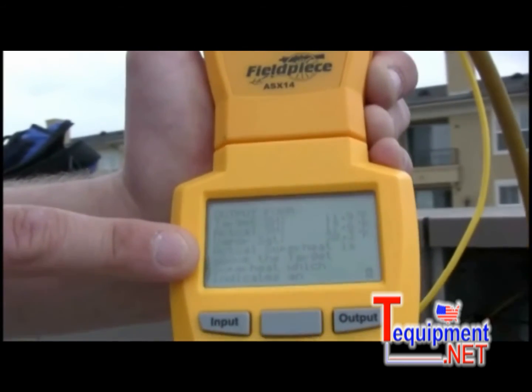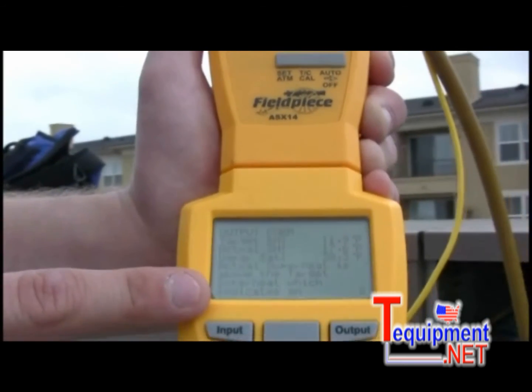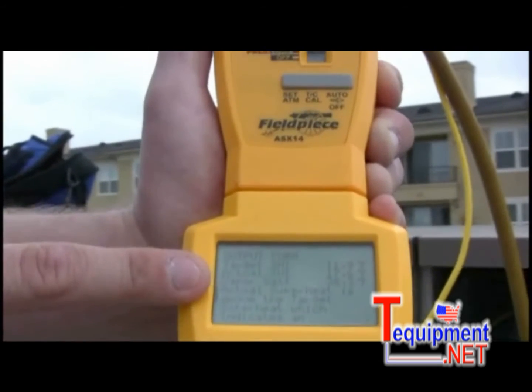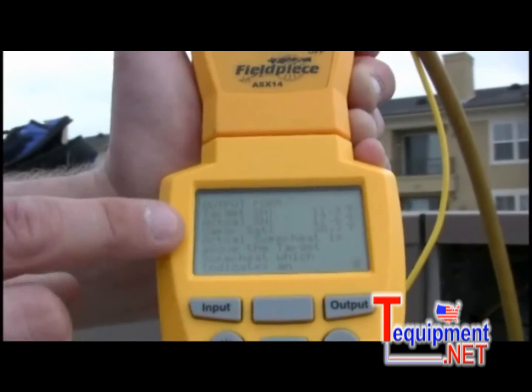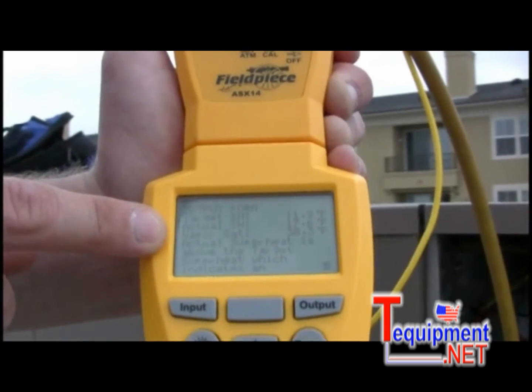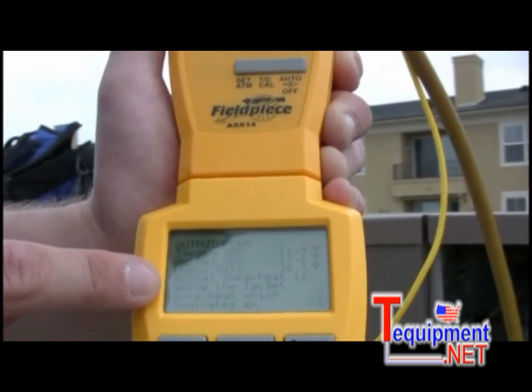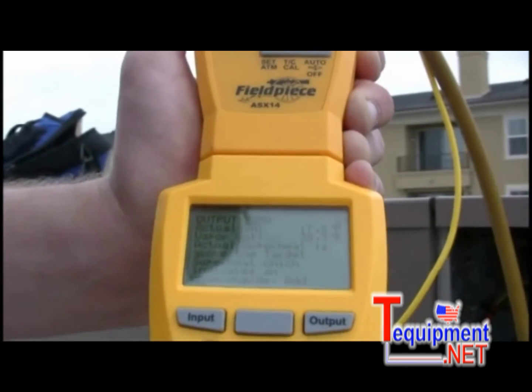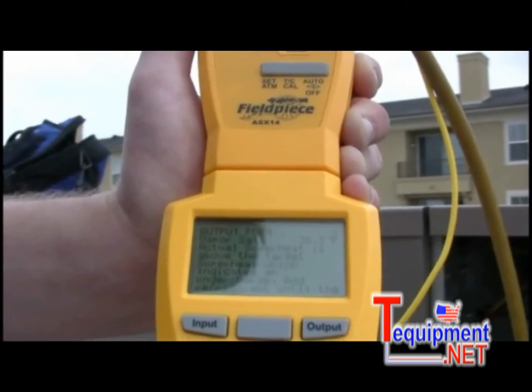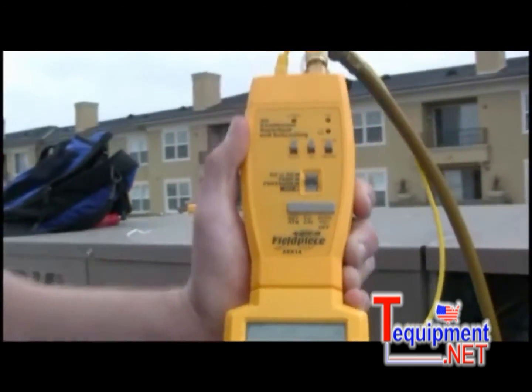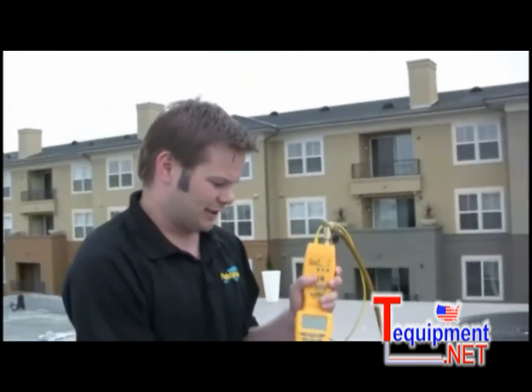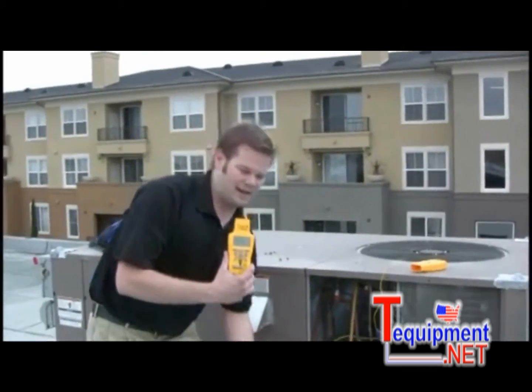Now this is pretty cool because what you can do is actually show your customer the instrument that tells you what's wrong with the system. So in this case, the system's actual superheat is above the target superheat, which indicates an undercharge. Add refrigerant until the actual superheat matches the target. So basically, we have the HVAC Guide telling us what to do.